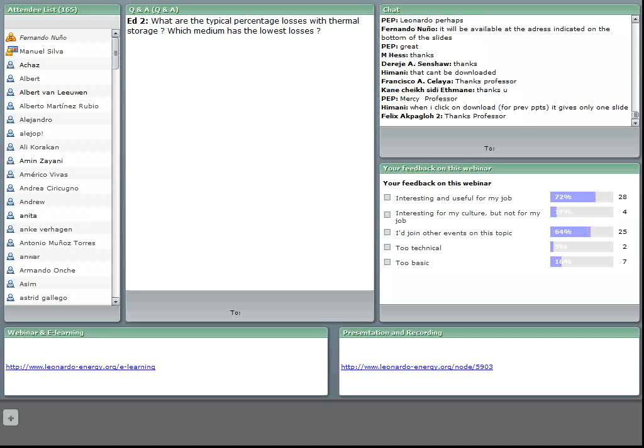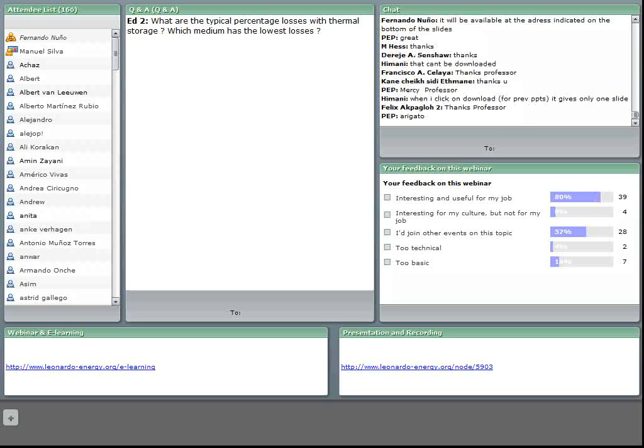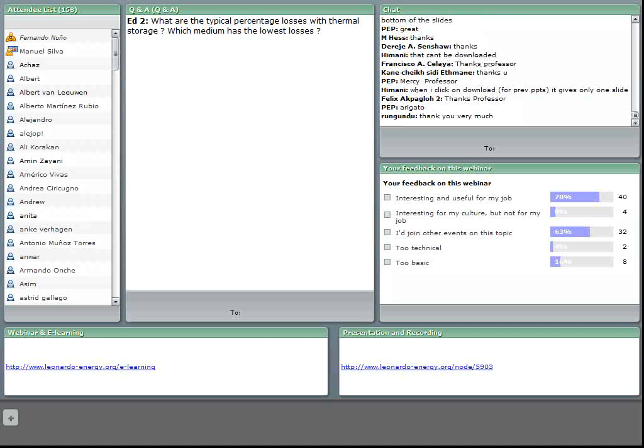Excuse me, I have some echo — well, now it's okay. That depends on the type of storage, on the temperatures, on the isolation of the storage tanks in this case. But normally the thermal losses of the tanks are rather low. If you use molten salt and the thermal energy is stored during the same day or the following day, the losses are less than 1%. That can also be measured in terms of the temperature decrease of the hot tank, which may be in the range of 1 or 2 degrees C per day.